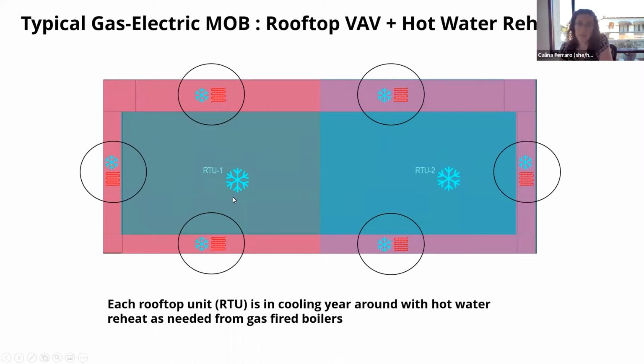That leads to a cooling and reheat cycle if we zone all of those on the same unit. We'd spend electrical energy to cool it in that conventional DX gas system, and then burn gas at a boiler to heat it back up. What we wanted to do was avoid two systems combating each other in those perimeter zones.